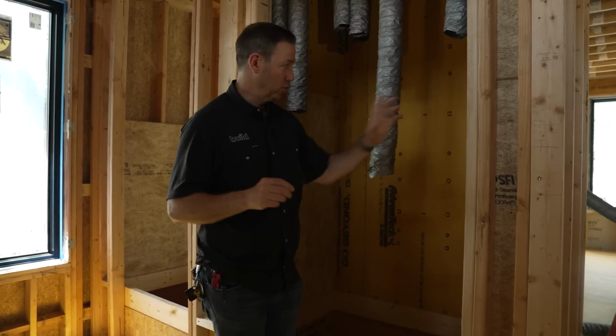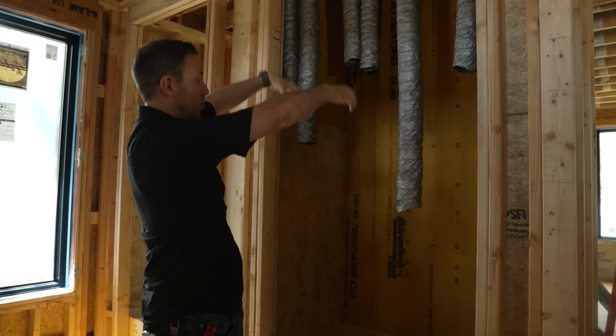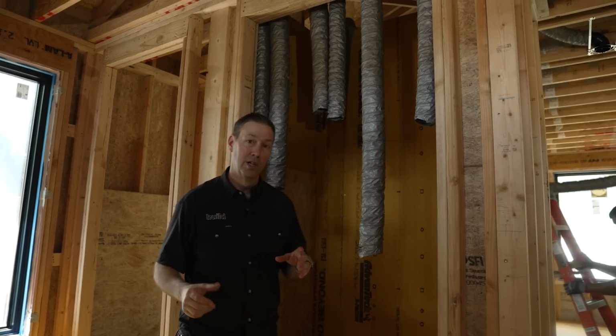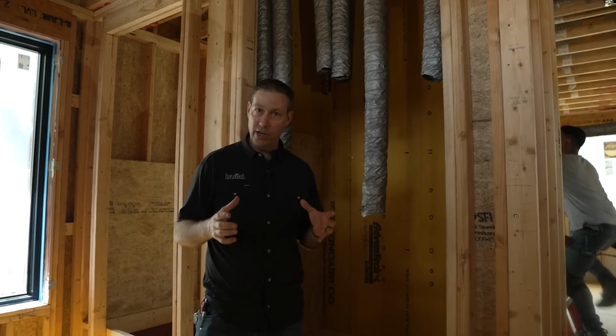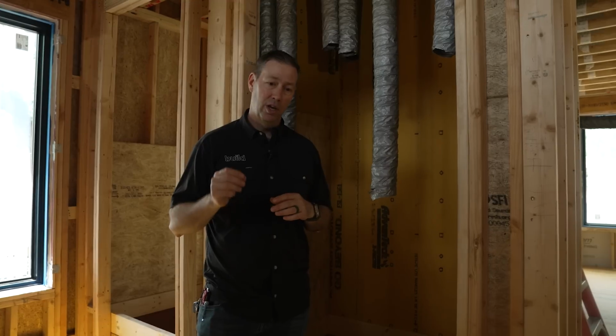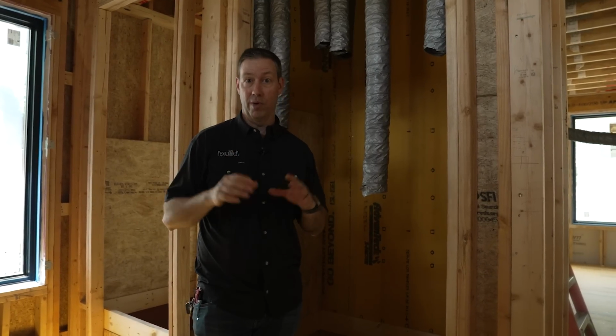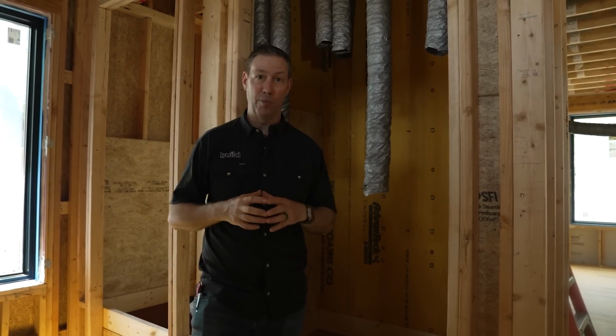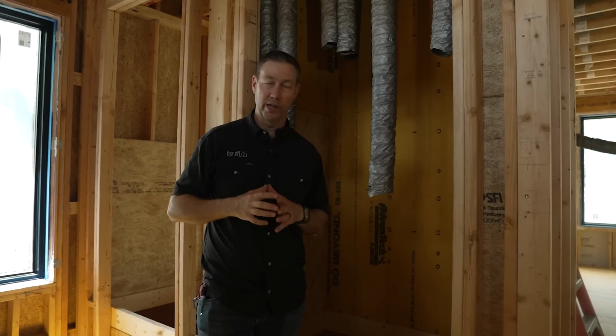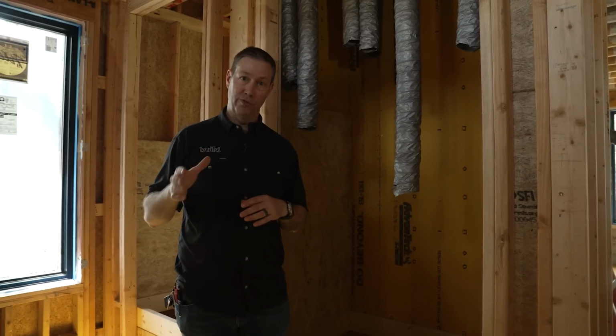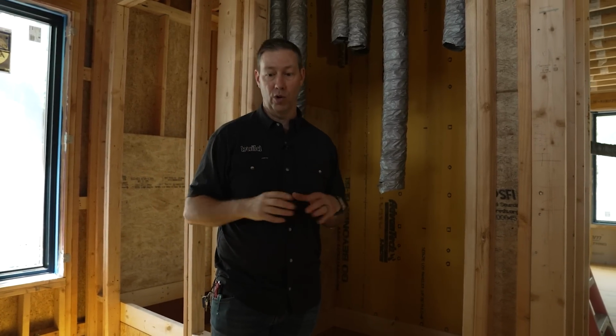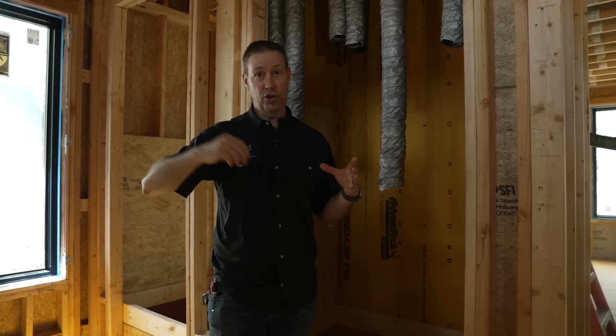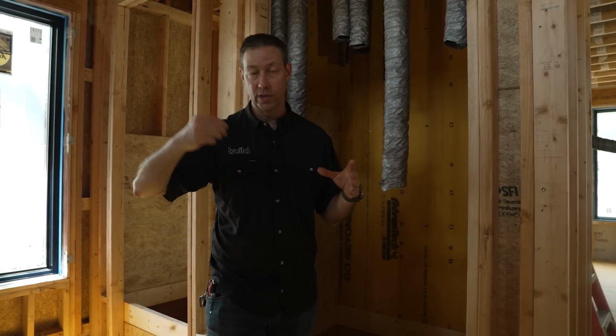Here's the deal on this Rheia duct. You'll notice a bunch of them coming in. We're early in the process, but this is a standard Carrier upflow system. I need to check my tonnage, I think the first floor in this house is about 2.5 tons. Our friends at Energy Vanguard did the manual J, so we know the exact output, and we gave that manual J to the Rheia folks, who gave us a full layout. Jeff, my installer, has had his iPad out showing the exact CFMs, the runs, and the locations.